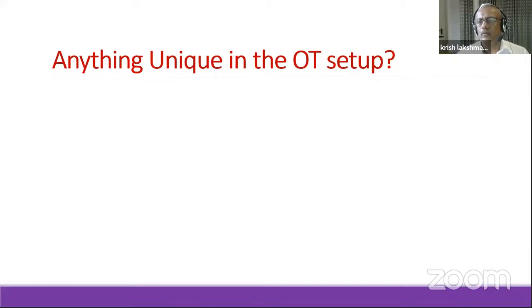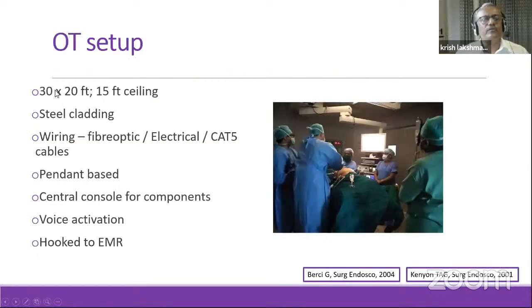Okay, why did I even talk about the pendant? Just like the floor area of the OT should be large, if you have something coming down from the roof, what should be high? The roof itself must be high, because if you have a low roof, the pendant won't give you enough gap between its bottom end and the floor. So in terms of the physical structure, you need a 30 by 20 feet room with a 15 feet ceiling.